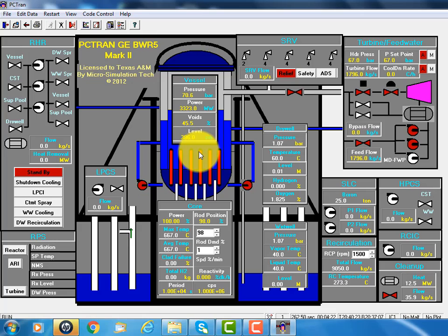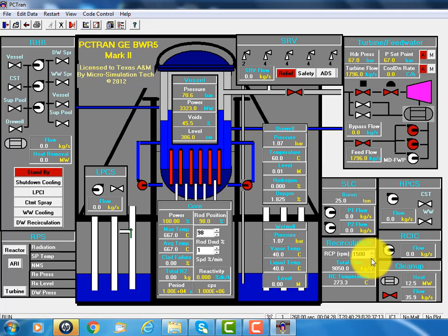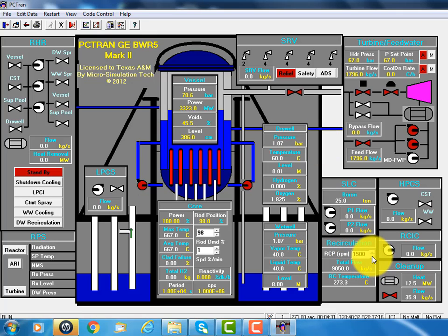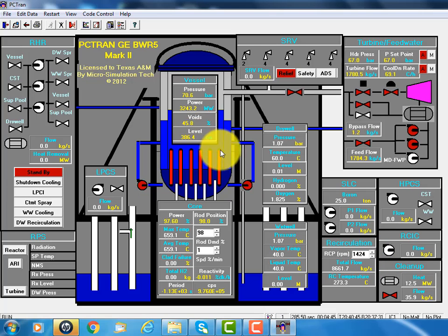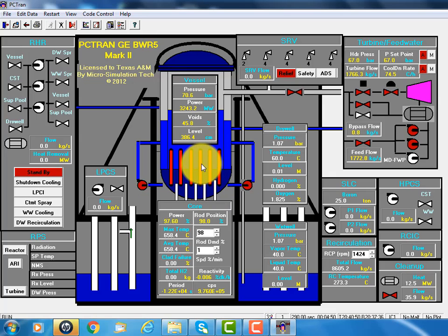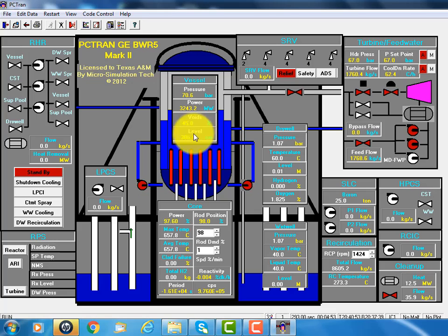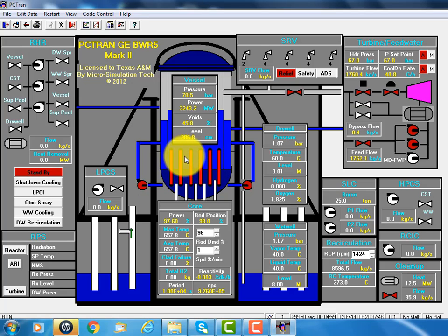Suppose we want to reduce the power, and for BWR, it's controlled by the speed of the recirculation pump. Full speed of 1500 RPM, rounds per minute. Now I reduce it to somewhere around 1400. You'll see the voids in the core increase because of the reduction of the flow inside the core. As a result, the neutron absorption will be less, and the chain reaction inside the core will be reduced.